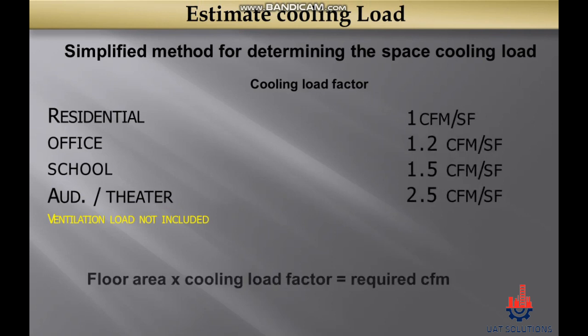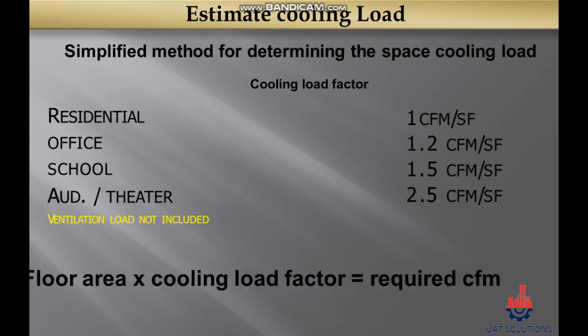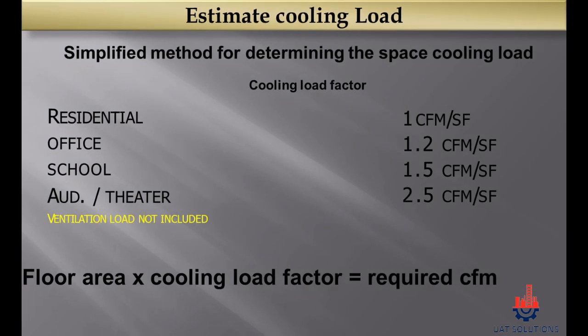The simplified method for determining the space cooling load is using the cooling load factors as shown. Residential buildings require 1 CFM per square foot. Office buildings require 1.2 CFM per square foot. School buildings require 1.5 CFM per square foot. Theater buildings require 2.5 CFM per square foot. The following formula can be used: floor area in square feet multiplied by the cooling load factor equals space cooling load.